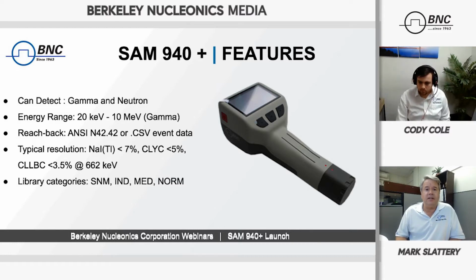Let's see, for the gamma, sodium iodide is the basic, really can do it all, the all-around champ. Sodium iodide at 2 inches and maybe even 1.5 inches. Resolution is about 7% at 662 keV.